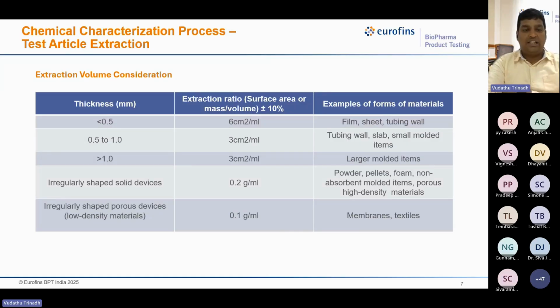Then extraction volume consideration. Extraction volume consideration shall be done based on basically two types of parameters. One is the surface area of the medical device, the other one is weight. If the surface area of the medical device can be measured, then the first choice is to consider the surface area. If the medical device is irregular in shape, then the second choice for extraction volume selection is based on the weight of the medical device. And whenever considering surface area, if the thickness of the medical device is less than 0.5 mm, then 6 cm² per ml is the ideal case to select the volume while extraction. Generally, examples for this are thin films, sheets, and tubing walls.